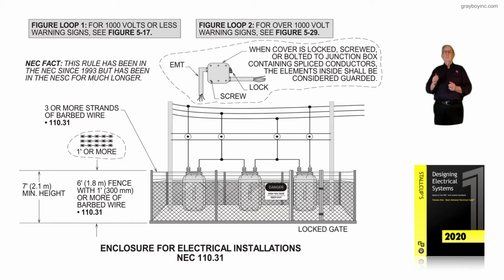Now, let's look at it this way. You enter into that gate, and those transformers are set up on pedestals, and usually what they do is they'll use a drainage metal type tubing, that you would use for drainage underneath the highway and so forth. And they would set that down, fill it full of concrete, so it's substantially strong, and they would set those transformers on top of that, and they would have the clearance rules that would meet the National Electrical Safety Code, Table 124-1. And then that label at the gate would be a red, danger label, danger, keep out.